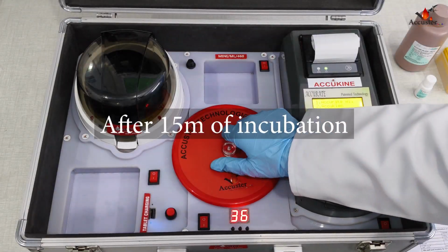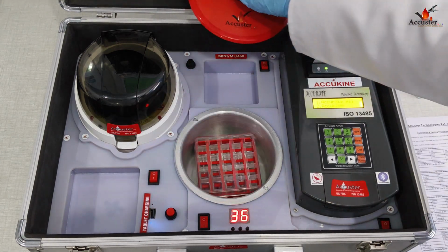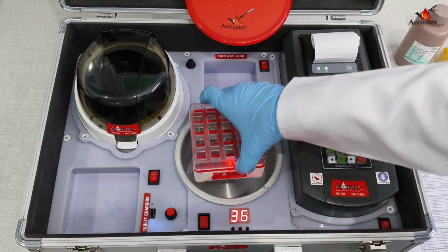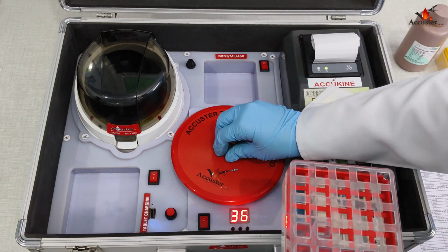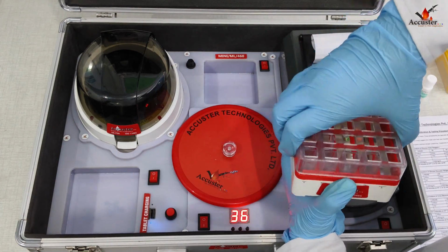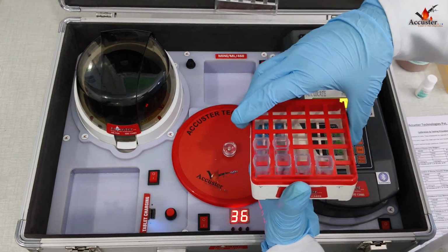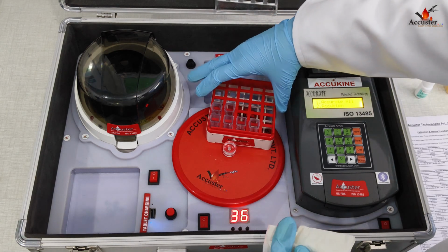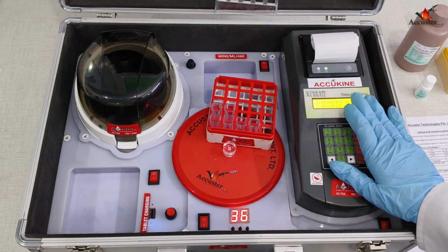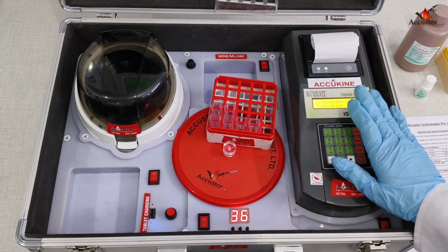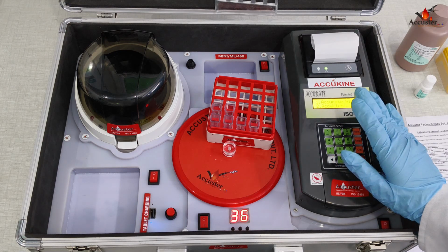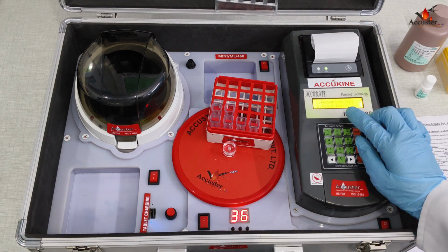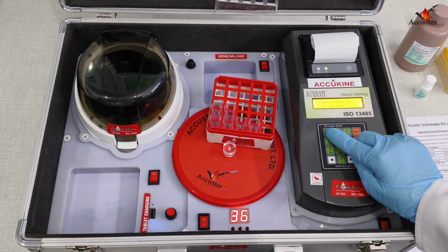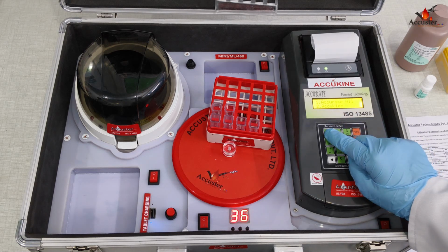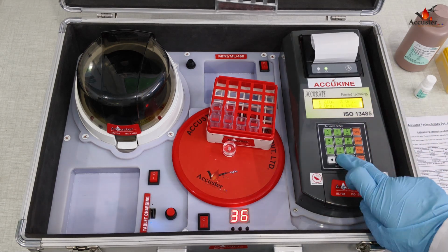After incubation, we will take out the cuvette containing calibration and quality control from the incubator. Then we will proceed to the biochemistry machine for calibration. On the display of the biochemistry machine, there are 2 options. First is Accurate All and second option is AccuKine. We will choose Accurate All and then press 0 to enter calibration mode.